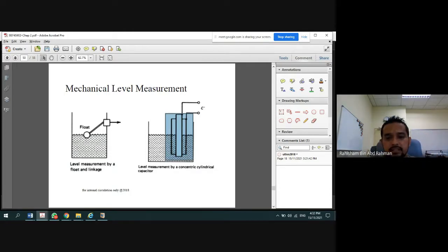We can also have a simple cylindrical capacitor. We install a cylindrical capacitor here, and then we can proceed with the measurement. This is another approach, where the fluid level within the tank determines the water level within this vessel, based on the capacitance values. The float and mechanical approach is the simplest one.